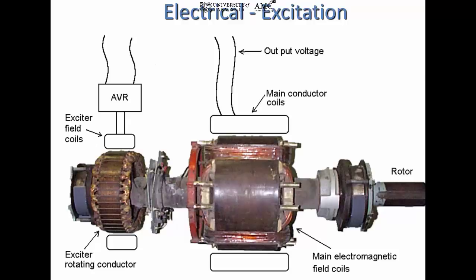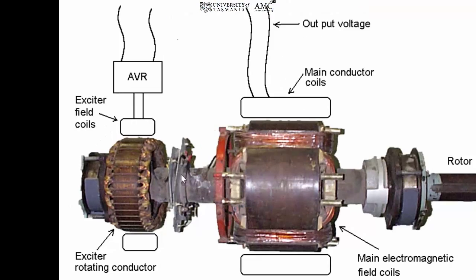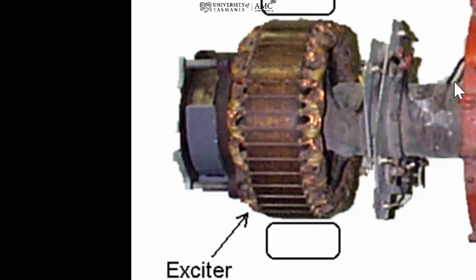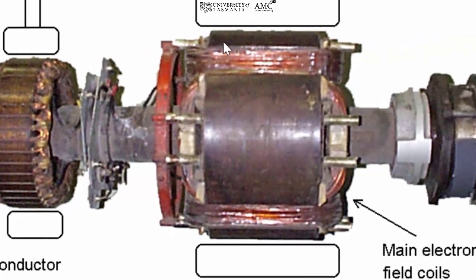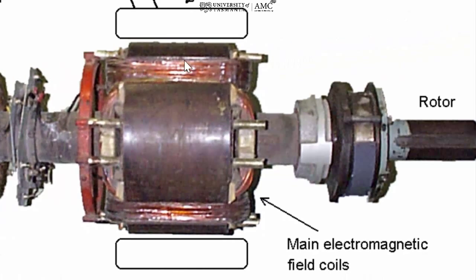Alright, so here we are with the rotor of our alternator, and we're going to show you a clip in a little while. Hopefully this will help pull it together, but we have what we call our exciter, and this provides the voltage in the form of DC for our field coils. Now here's one. So this is the electromagnet. This is the winding around our soft iron core. So that's one pole or field coil, here's another, and here's another.